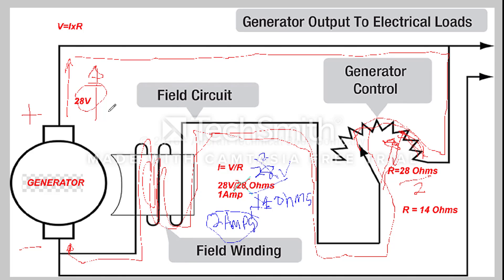So the generator control is effectively changing our output voltage by increasing or decreasing our resistance, which changes our value of voltage. In the next video we're going to talk about a carbon pile voltage regulator that does this automatically. To summarize: if we decrease resistance, we increase output voltage. If we increase resistance — by increasing the length of the resistor — we decrease current and we decrease output voltage. If we decrease resistance, we increase current, increase the magnetic field, and increase our output voltage.